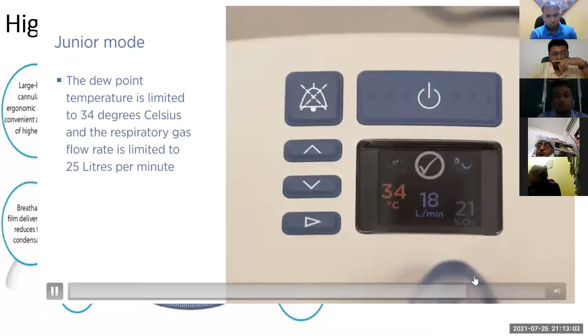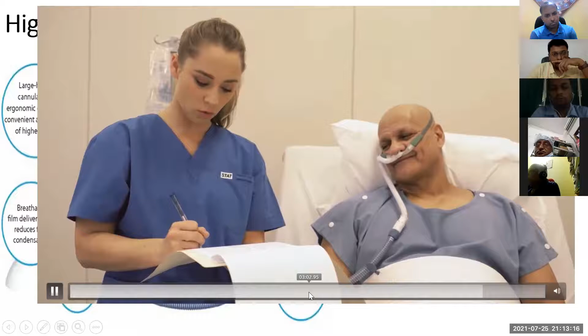As with any medical device, you may need to make adjustments to the EVO2 as the patient's condition changes. Keep in mind that the patient's breathing pattern can affect the fraction of inspired oxygen. For this reason, you should always use a pulse oximeter and adjust the oxygen flow rate to maintain the appropriate blood oxygen saturation in your patient.